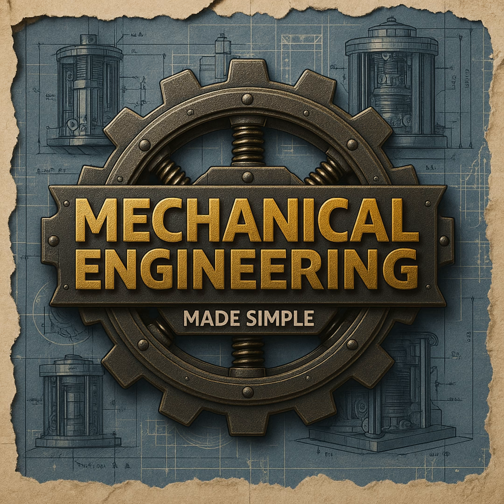And when designing a new system, you can't just aim for the expected load, right? You need margins. Absolutely, you need some headroom. The general guideline is, for water-cooled compressors, add about a 30% capacity margin over your calculated system demand. And for air-cooled, bump that up to 40%. Air-cooled machines are more sensitive to ambient temperature swings, so they need a bit more buffer. Now, you can trim these margins back, but only if you have really solid historical data from your specific plant showing exactly what your air usage patterns are. Otherwise, stick to the 30 or 40%.